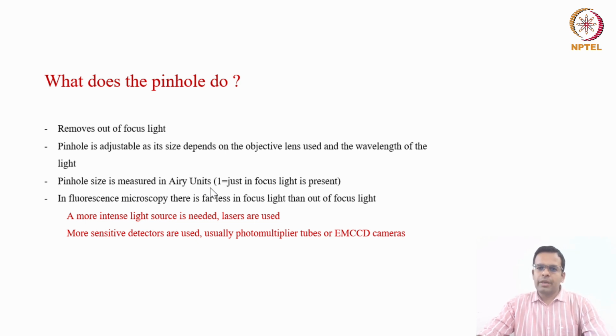Okay, so the pinhole is just a closed circular ring, and the diameter of that ring is adjustable. You can keep it open for one Airy unit, or for two Airy units, or any point in between. Ideally, one Airy unit is preferred because that only collects the in focus light. I will explain more about these Airy units and the pinhole.